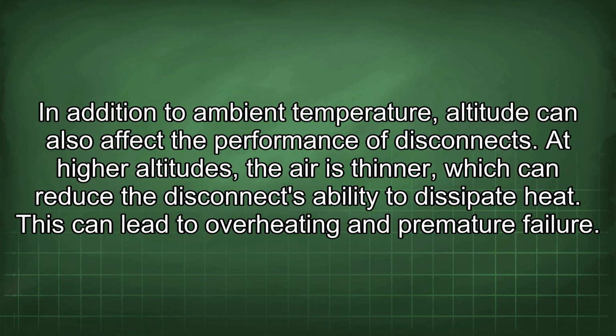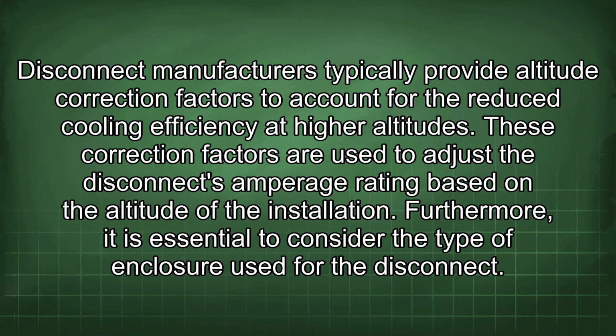In addition to ambient temperature, altitude can also affect the performance of disconnects. At higher altitudes, the air is thinner, which can reduce the disconnect's ability to dissipate heat. This can lead to overheating and premature failure. Disconnect manufacturers typically provide altitude correction factors to account for the reduced cooling efficiency at higher altitudes. These correction factors are used to adjust the disconnect's amperage rating based on the altitude of the installation.